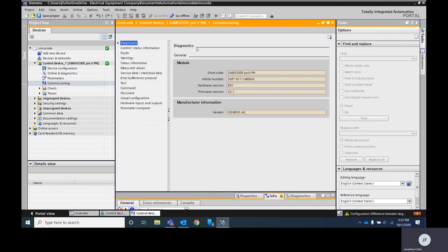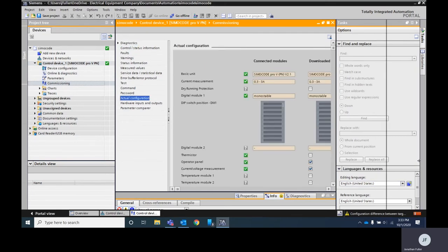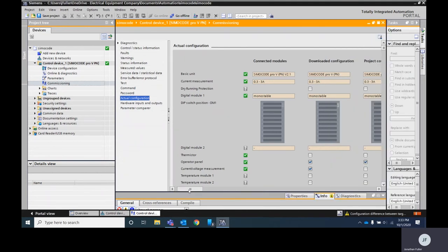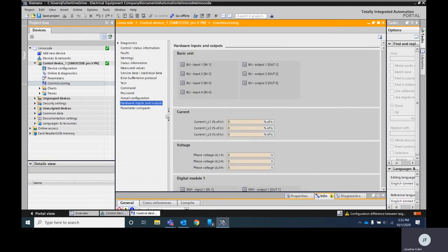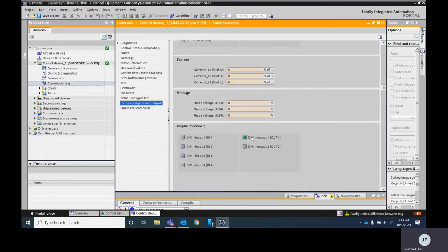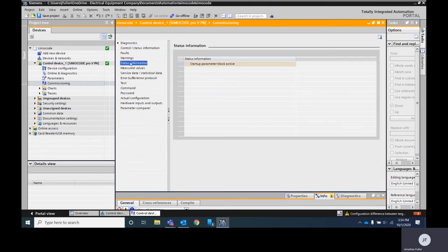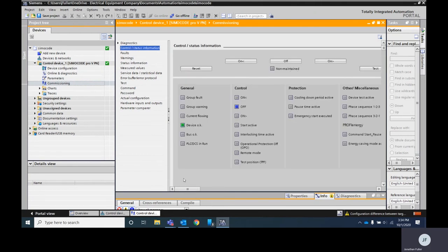Now notice that I've got that orange bar here in TIA Portal which means I'm online as well as this green check over here on the left hand side. Now if I were to go into my SIMOCODE and look at some of the items you'll see here it actually shows me what I have connected to my device. I can go in here and check my inputs and outputs make sure that I have them wired correctly for push buttons and other things. You'll see here I've got an output wired off my digital module. Then I can actually go in here as well and set any faults or warnings that I want on my device or see any that I have currently.